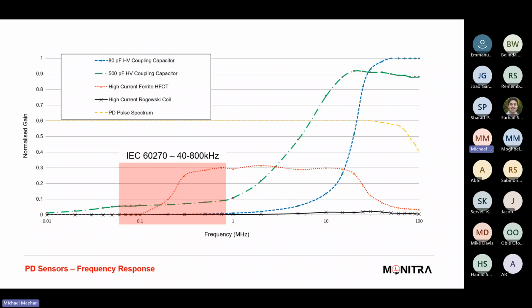There are other frequency ranges which people use, non-IEC, but still very useful, which give you the benefit of seeing maybe deeper in the winding, and some people will test at 2 to 20 megahertz and also 20 to 200 megahertz.